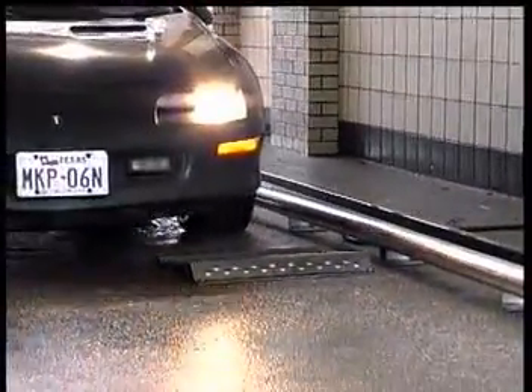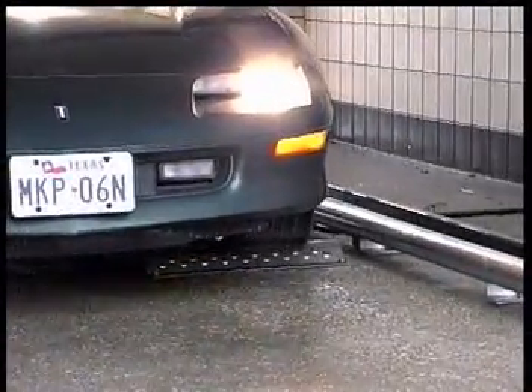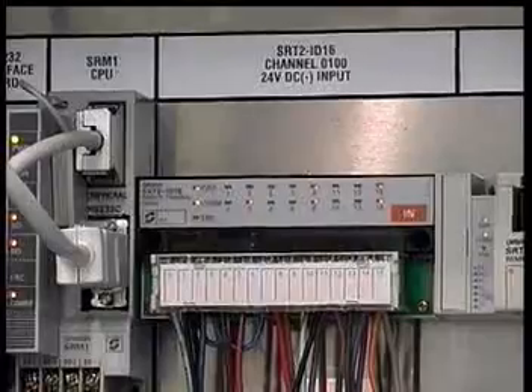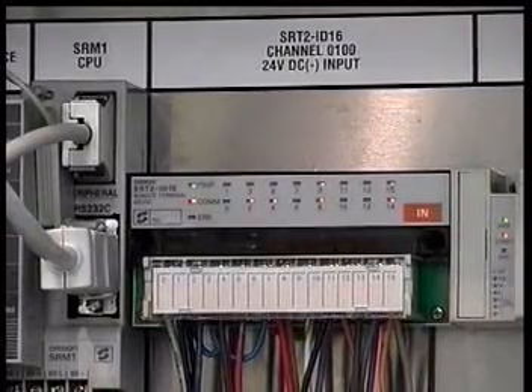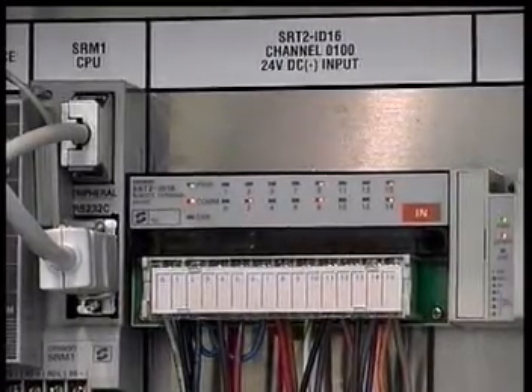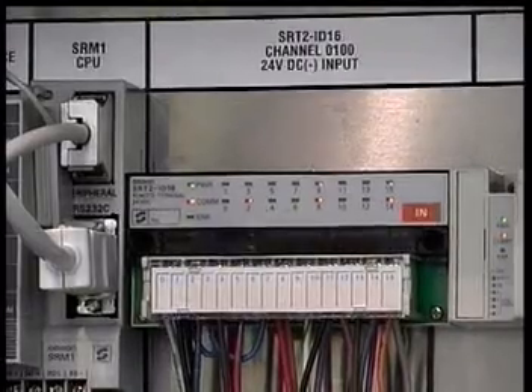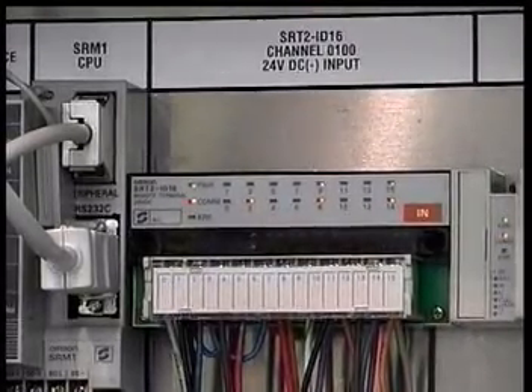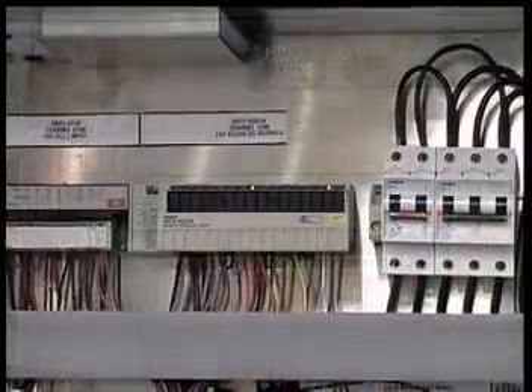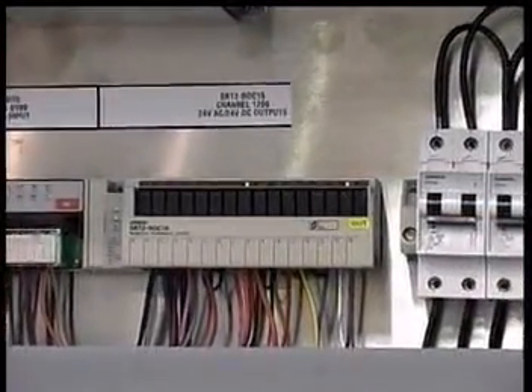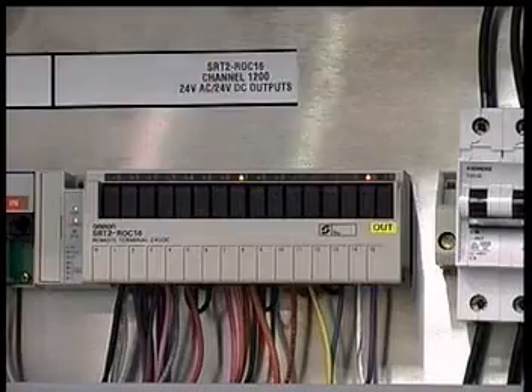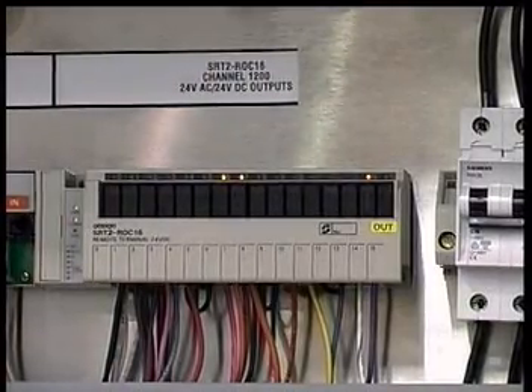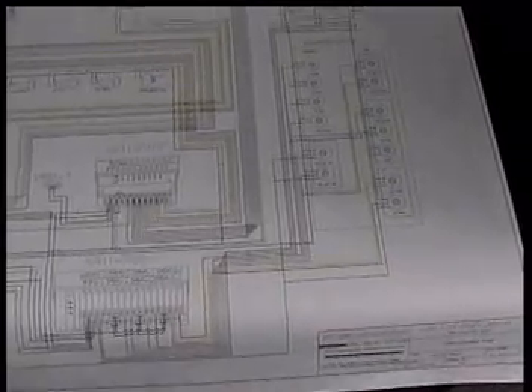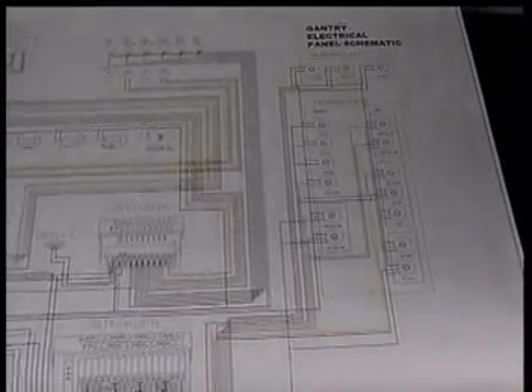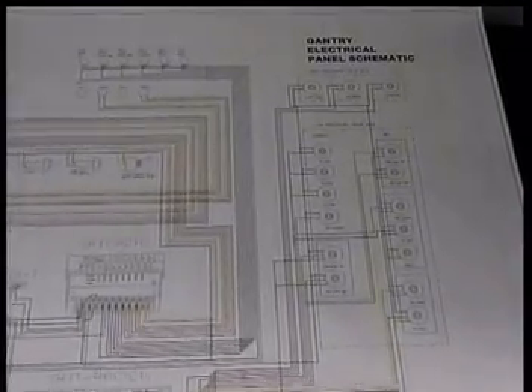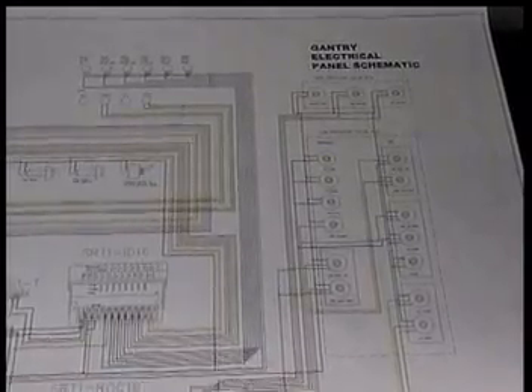Anytime an electronic switching device, such as an optic eye or proximity switch, has been activated, the electronic signal created is received by the input card. This signal will be indicated by the LED above the corresponding wire number. The signal is then sent to the processor. When it is time for the gantry to move or a valve to open, the processor directs the output card to send an electronic signal to that function. There are different voltages used in the output cards. The electrical prints located in your manual and on the panel doors clearly define their location.